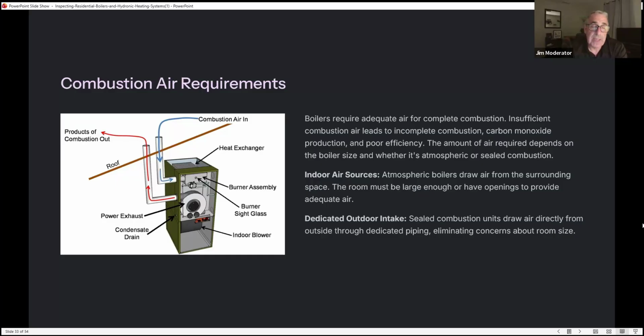This is something that you're not going to do the math on, but after a certain number of inspections, you're going to go into a room with a boiler that does not have enough combustion air, and you're going to note it. A lot of times you'll see them in closets or whatever. You want to see louvered doors. You want to see exhaust air, like the fan in the can, so that you can get air from the outside. So use your common sense. If your spidey sense goes off and you think the room's too small, there's not enough combustion air, you can't go wrong saying that. The worst thing is your client will call you and tell you, my heating contractor says it's fine. Well, good for you. That's good.